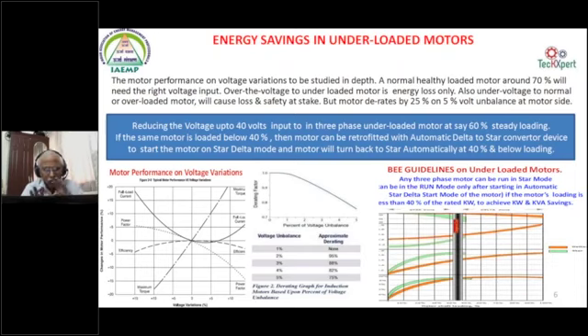Let us say I am assuming all the motors in our industry are equally balanced. Theoretically, a motor is meant as an equally balanced three-phase machine, but normally it does not happen. That is why we go for a three-phase four-wire meter to measure the current unbalance, the negative phase sequence component, and to see the motor consumption as such. Assuming the motor has an unbalance of around 5%, automatically a 10 HP motor gets derated to 7.5 HP.